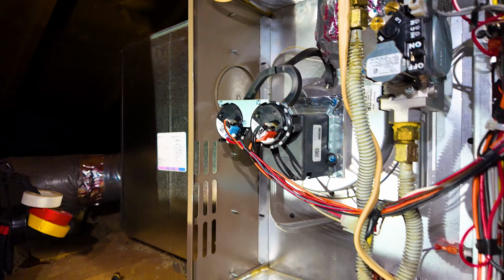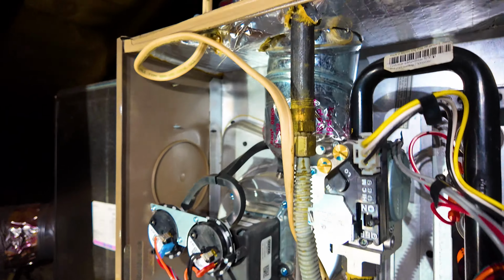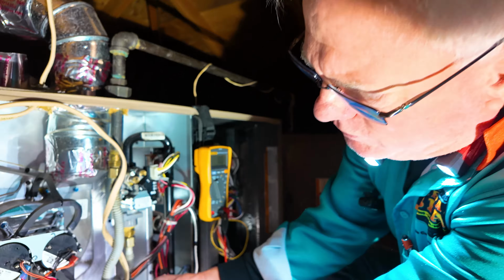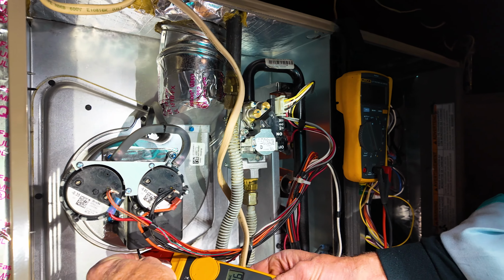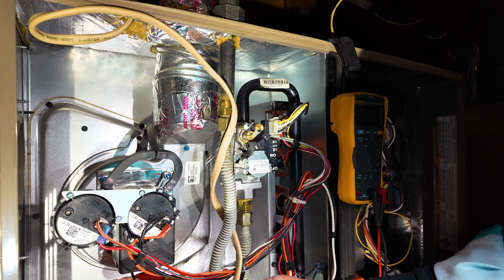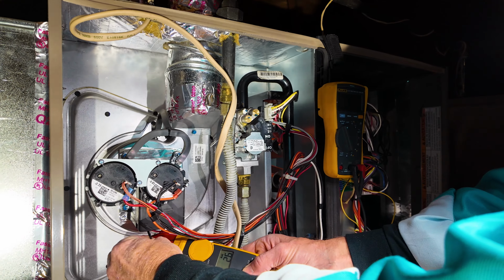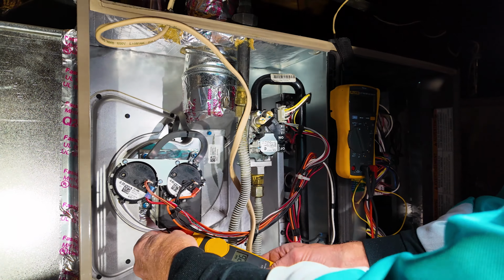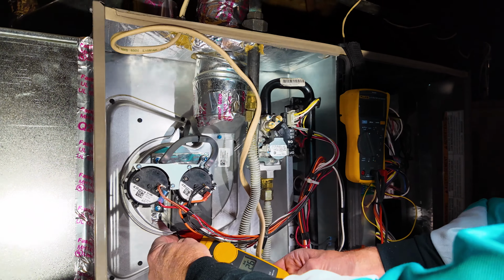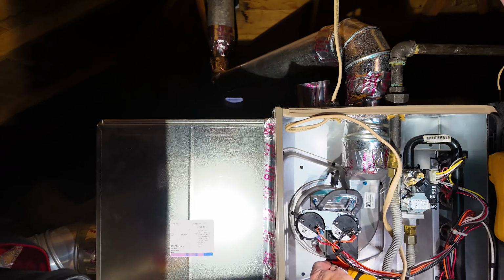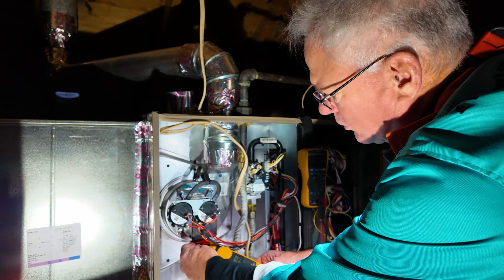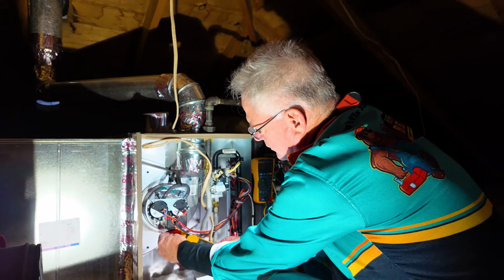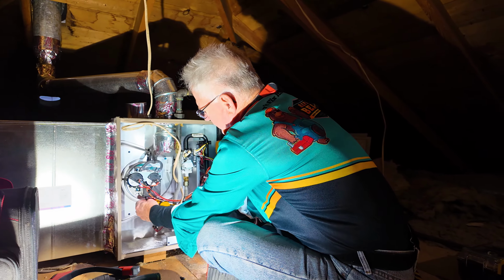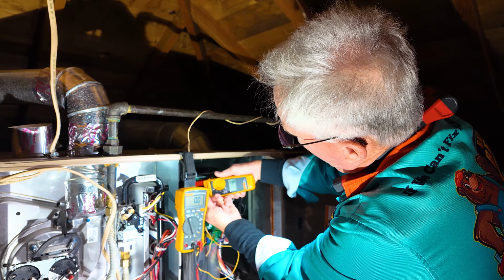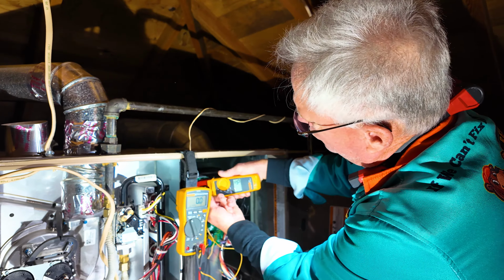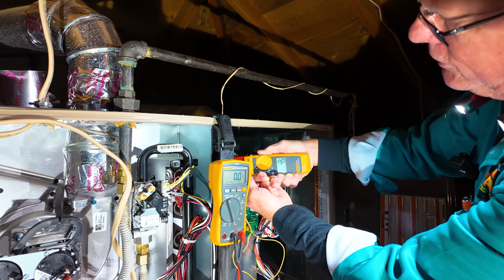And I'm going to let it run for a minute and make sure that there's not something else that needs to be done. The inducer fan is pulling 2.6 amps, which is good. And then it's going to go into low stage. Once everything lights up, we're going to watch this amperage drop back down. When it goes to low stage, it'll drop down to like 0.4. It's still at 2.9 on the inducer. The burners are burning. Okay, it just cut down to 0.8 now on the inducer motor. Okay, on the blower motor, we're pulling 4.6 amps with the door open here, so that's all good.